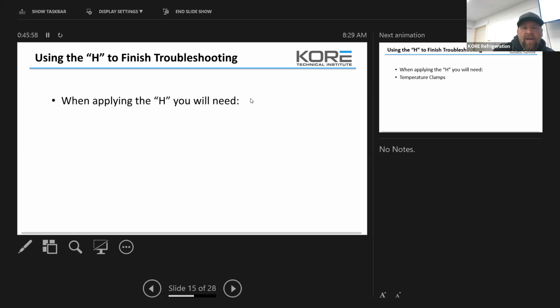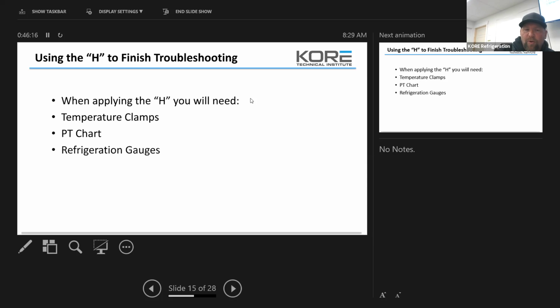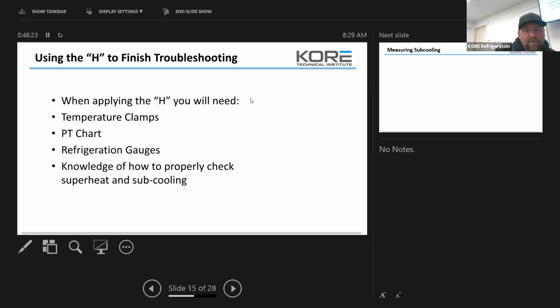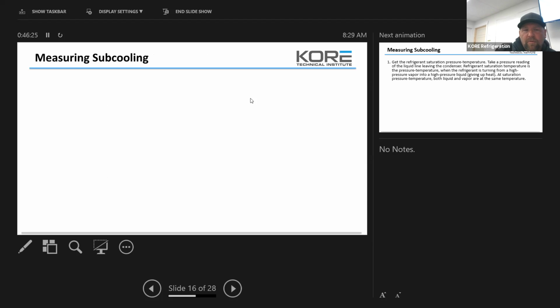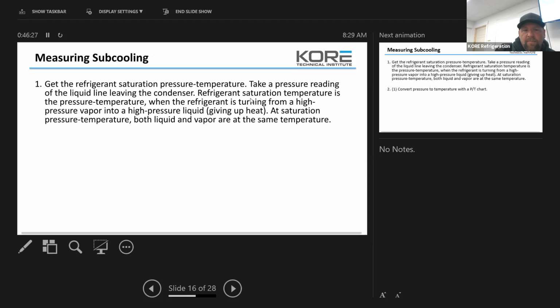So when you're applying the H, you need to use temperature clamps. I've seen guys try to tape K thermometers to the pipe. You're not going to get a true reading. Spend a little bit of money and make an investment in clamps. A PT chart. We're going to go through the old school way of actually having to use a PT chart and convert. So refrigeration gauges and knowledge of how to properly check superheat and subcooling. So, measuring subcooling. Where are we going to look at subcooling, guys?